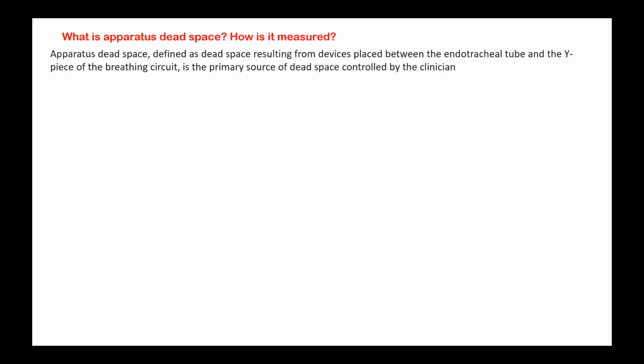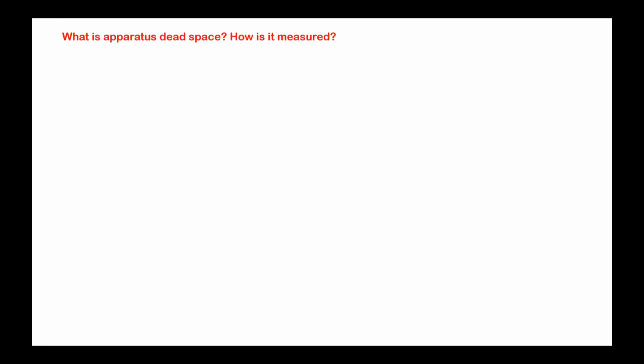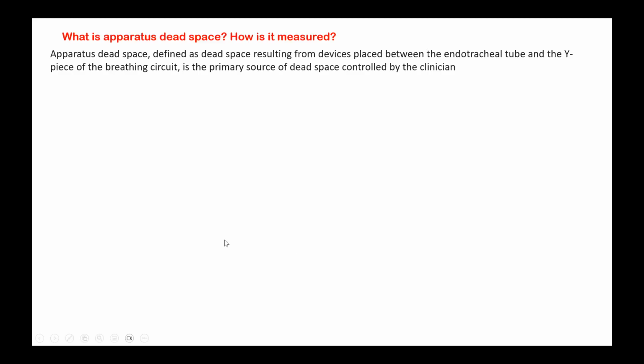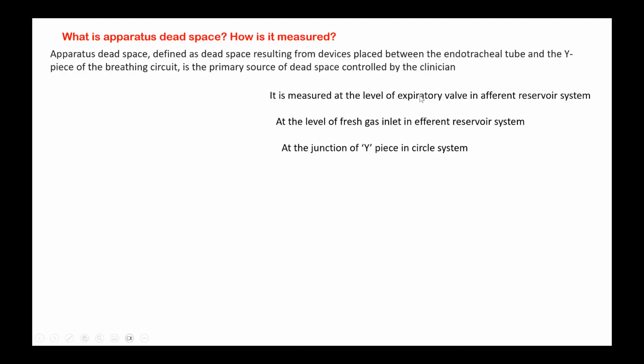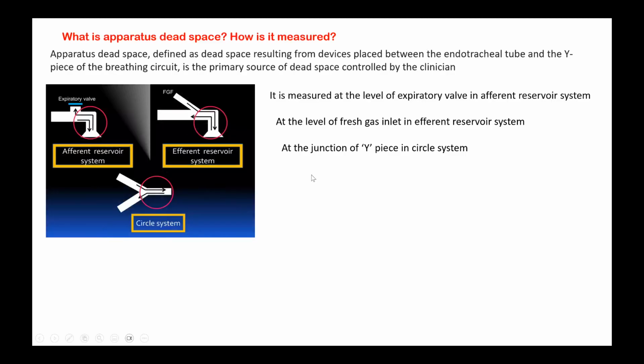What is apparatus dead space? How is it measured? It is dead space not taking part in gaseous exchange, caused by the machine or the connections. Okay? It's measured at the level of the expiratory valve in the afferent reservoir system, or at the point of entry of fresh gas flow. So this is called the afferent reservoir system, and this is the expiratory valve. This is the efferent reservoir system, the fresh gas flow entry. And in the circle system, it is at the junction of both the inspiratory and expiratory limb.